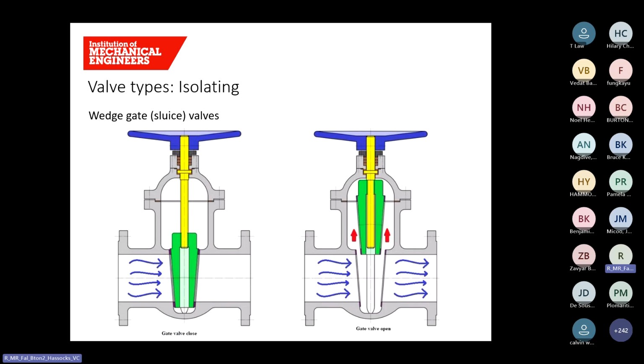The valve is operated by rotating a threaded stem multiple times. This slow, deliberate motion helps avoid sudden pressure changes. Operating the hand wheel turns the stem, which raises or lowers the wedge-shaped gate. Here on the left, you can see the wedge gate valve closed, and on the right, you can see it fully open.